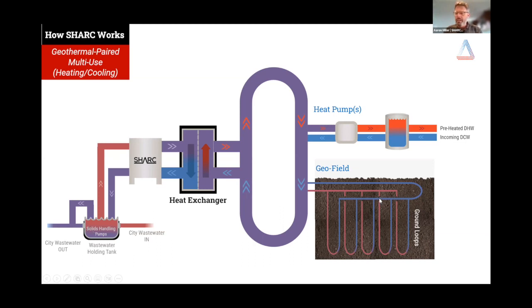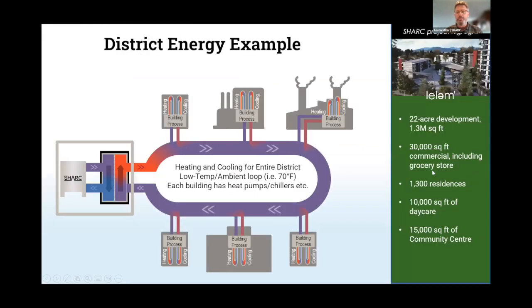So in essence, like I said before, the SHARC is a rural, suburban, urban geofield. We're able to pair it up with a geofield for new construction. As Yanning mentioned before, the upfront cost of boring those holes is massive. By using the SHARC tied between a sewer or some wastewater energy source and the geofield, we're able to reduce the number of boreholes by up to 40 or 50%. So the upfront cost of that project gets slashed precipitously.